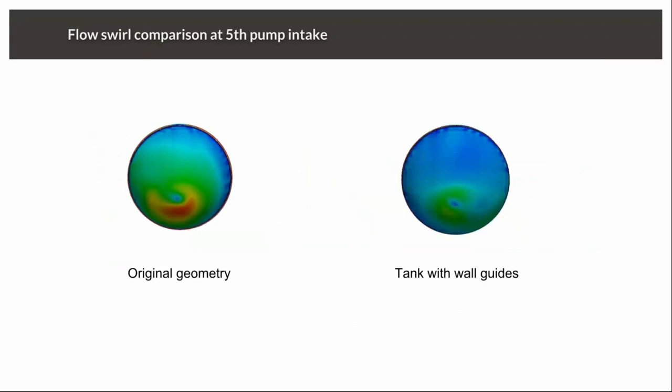The next important parameter for these sump computational model studies is the calculation of swirl angle. The Hydraulic Institute Standards state that the swirl angle should be less than five degrees. For the original geometry, the swirl angle was really very high — especially for the fifth pump where the columns were causing flow separation and thus increasing the swirl angle. After subsequent modifications to the geometry, we found that the swirl angle was reduced to a great extent and is well within the acceptable limit.